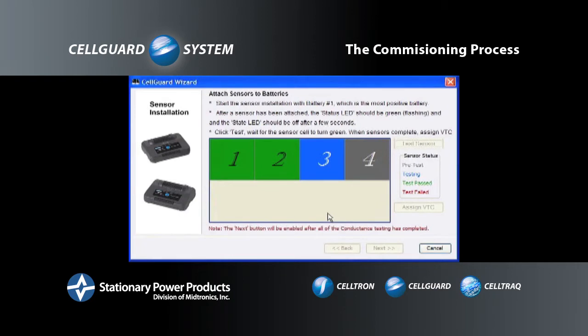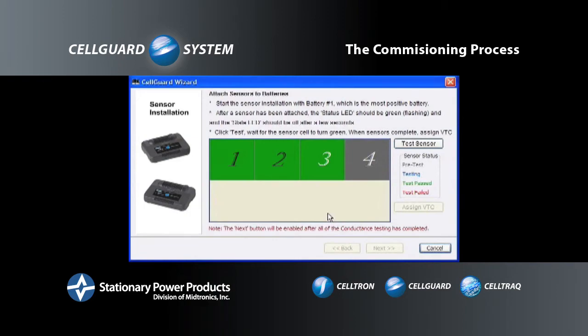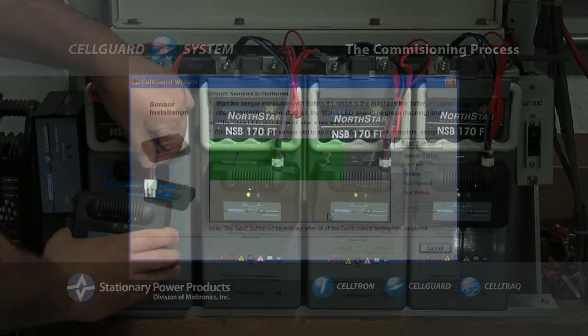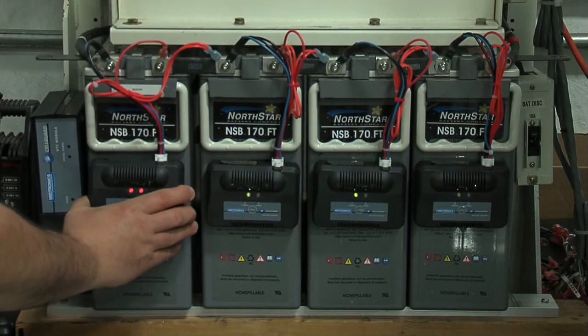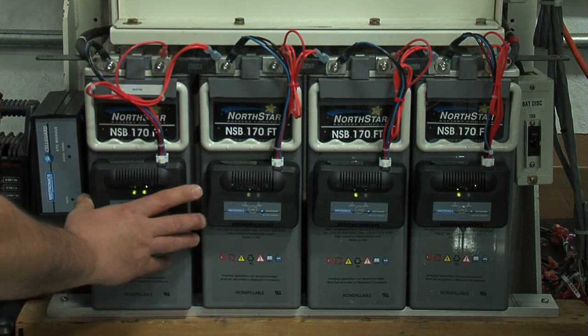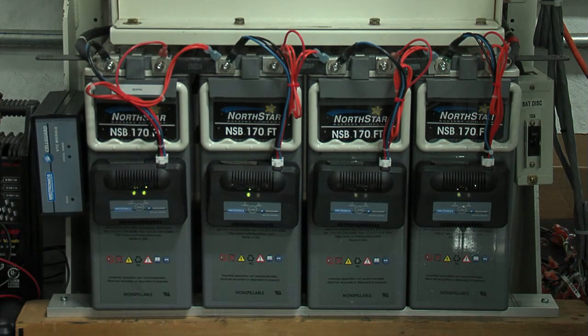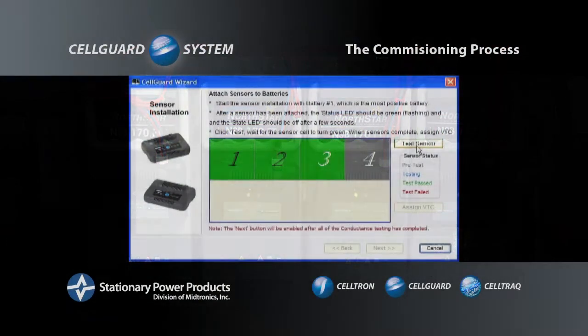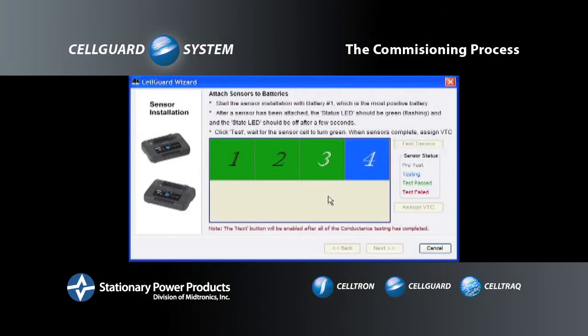Wait for the square for sensor 3 to turn green, and then connect the sensor for battery 4. Wait for the LEDs to go through their power-up sequence. When ready, click Test Sensor to commission sensor 4. The square for sensor 4 is now blue.